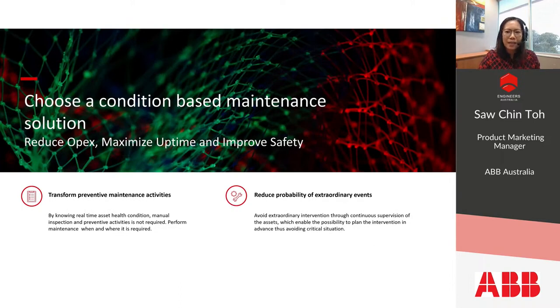Now, how can condition-based maintenance help? By knowing the real-time asset condition, we are able to transform time-based preventive maintenance into an advanced maintenance technology. We can carry out risk assessment based on the condition of the asset, which is available 24/7, and only perform the necessary maintenance when and where it is required. This will reduce the maintenance costs, for sure, because periodic manual inspection is no longer required.